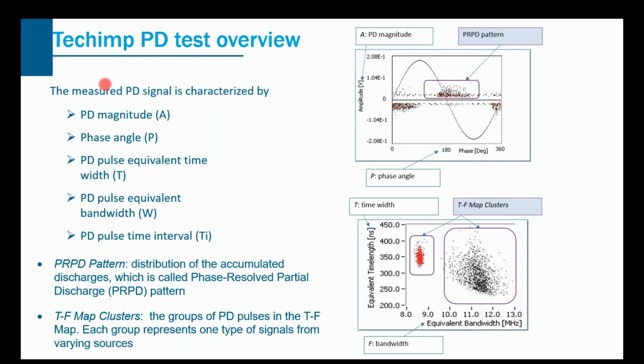So with those parameters, how do we use them? Why do we save those parameters? The phase resolved pattern is a very classic PD diagnostic and analysis tool, as shown here. It uses the first two parameters, the magnitude and the phase angle. Each acquired PD pulse is presented by a dot in this chart, with the pulse magnitude and the phase angle relative to the power frequency. So we can see some clusters or distributions of the pulses, and this cluster or distribution is an indicator of the defects.